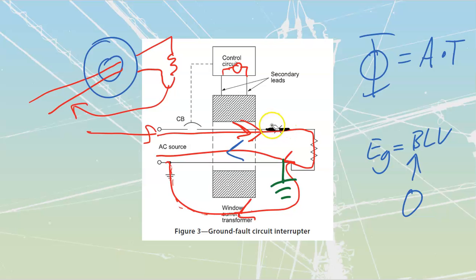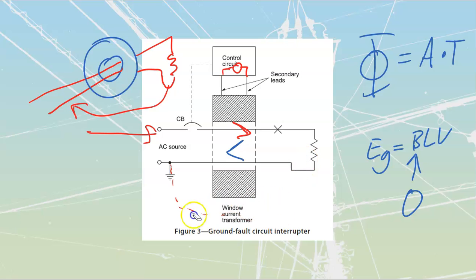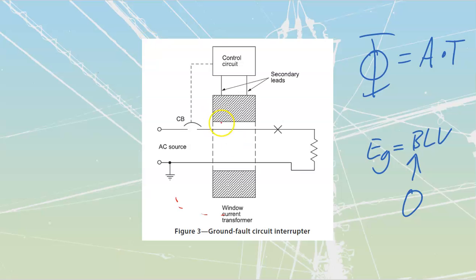If this was a GFCI breaker, to take this down to that point of being a GFCI breaker, what happens inside of our panel, let's say that this is the connection side. We know that this one's going to go to my line. I'm drawing that poorly there. This connection over here is going to go to my line. This connection over here is going to go to my neutral inside of the panel. This could be that pigtail that we're taking a look at. This side over here is going to be my brass screw, my hot screw. This one over here is going to be my nickel screw, my silver one, or my neutral.